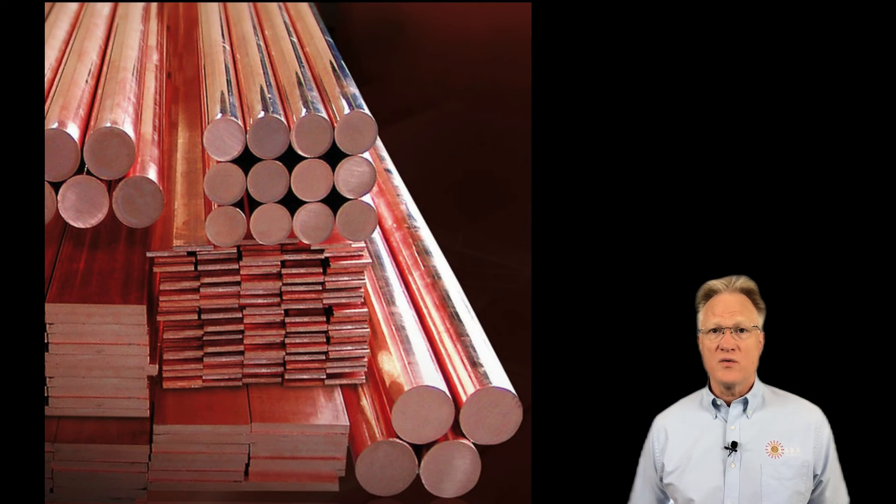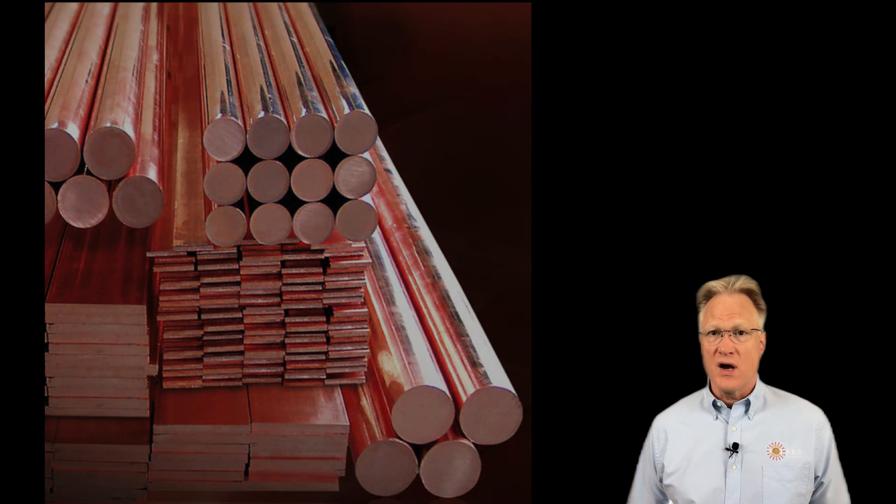Remember, round wire has high inductance when compared to flat ribbon cable conductors. Use ribbon where it's practical and use the most direct path to the facility's master ground structure, preferably the AC service's ground rod or its associated ground ring.